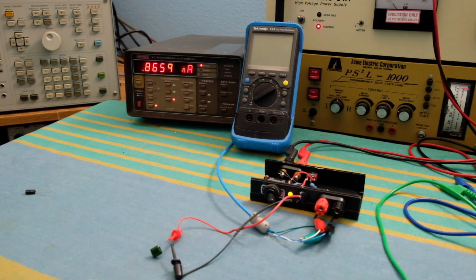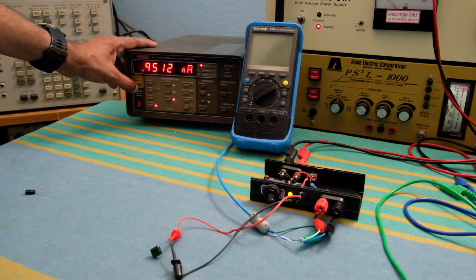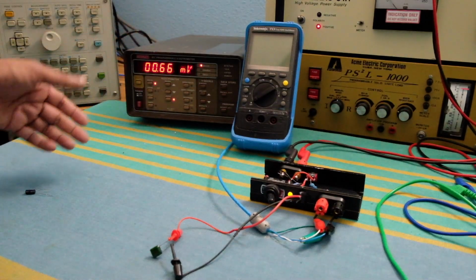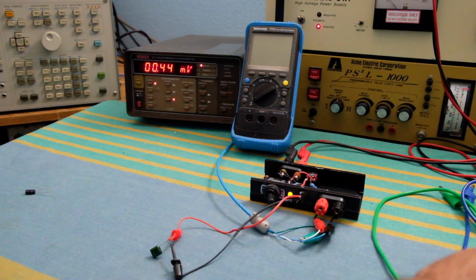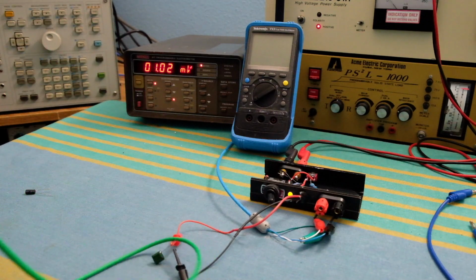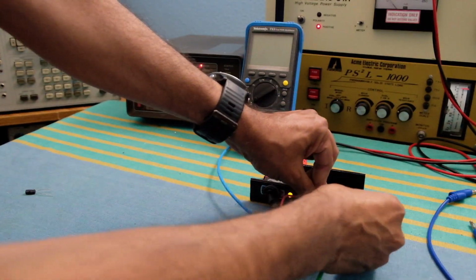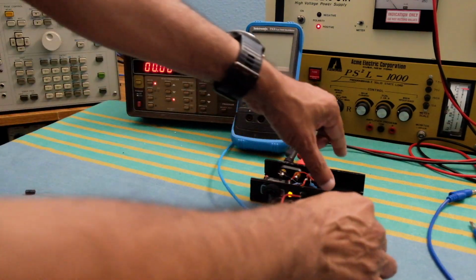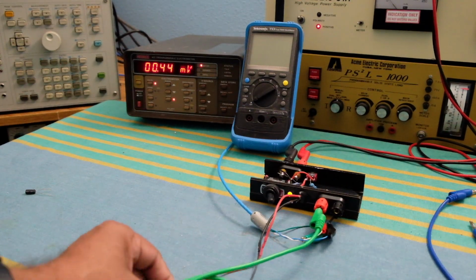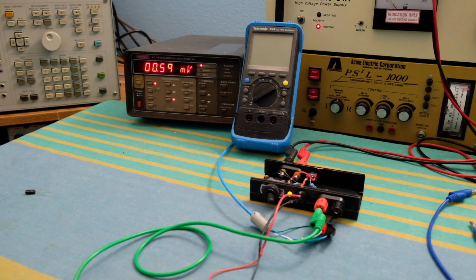Now I'm going to measure the voltage and see the voltage method. So for that, I'm going to switch this to voltage. It's almost fully charged now, so go to volts, and of course it's going to read similar values in millivolts. So if I short this out, now I've fully charged the cap, and then I'm going to remove this one, and you'll see that it's a similar level, 1 millivolt or so. It's quite noisy and it's not as good as the current reading, but it gives you similar values, about a millivolt or so, which translates back to a nanoamp, because it's a 1 megaohm resistor across the ammeter terminals. So this is another way of measuring the same thing using voltage.